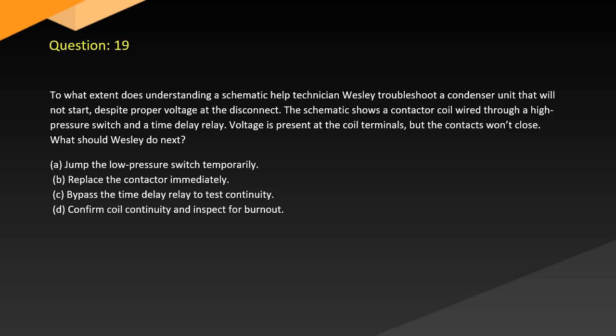Question 19. To what extent does understanding a schematic help technician Wesley troubleshoot a condenser unit that will not start despite proper voltage at the disconnect? The schematic shows a contactor coil wired through a high-pressure switch and a time delay relay. Voltage is present at the coil terminals, but the contacts won't close. What should Wesley do next? A. Jump the low-pressure switch temporarily. B. Replace the contactor immediately. C. Bypass the time delay relay to test continuity. D. Confirm coil continuity and inspect for burnout.